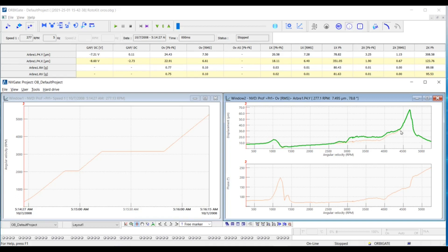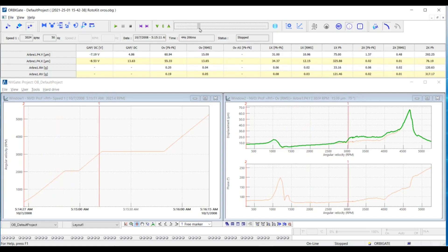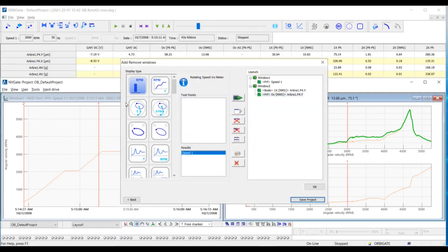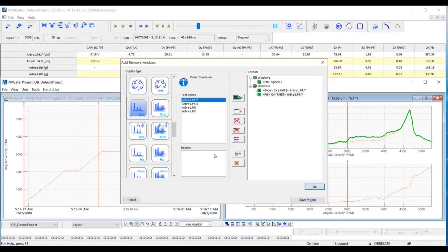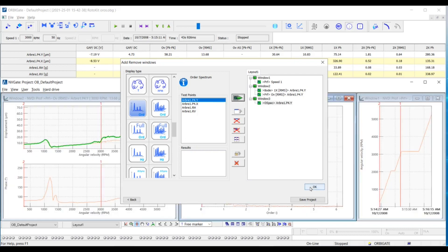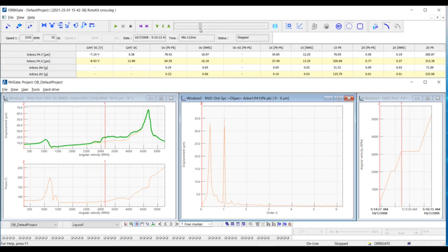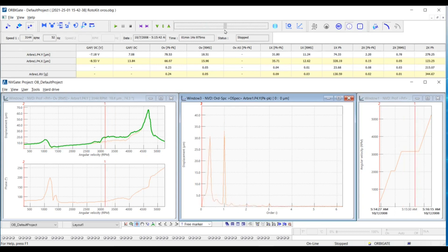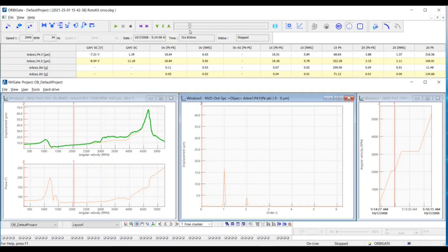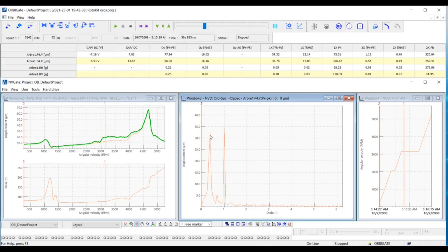I would like to overlay the 1x RMS and the overall RMS. I expect to have the same plot because I assume that the resonant energy will follow the 1x. I would like to understand what happened over this large range, so I will display the order spectrum. I select the add windows function for orbit and choose the order spectrum of my Y probe, which allows me to use my cursor to browse my measurement. On the far right graph, I can browse through my speed profile to speeds greater than 3000. Just before 2000 RPM, I have only 1x as you can see on the order spectrum, but as soon as I enter into this speed range, I have one subharmonic with an order of 0.375. So it appears that I have an oil instability.